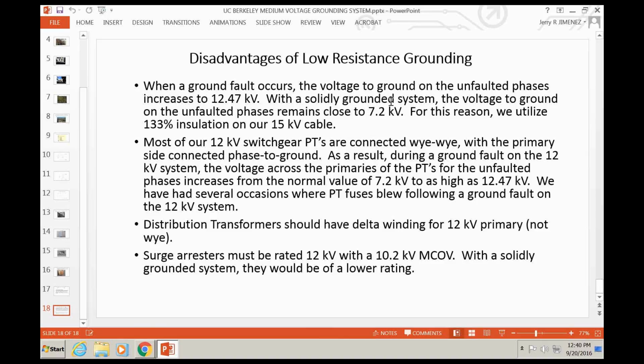However, with a solidly grounded system like the one we used to have a long time ago, the voltage to ground on the unfaulted phases remains pretty close to 7.2 kV. Again, it may get a little higher. And for this reason, we use this 133% insulation on our 15 kV cables because they're subject to a little bit higher voltage to ground because of this low resistance grounded system that we have.